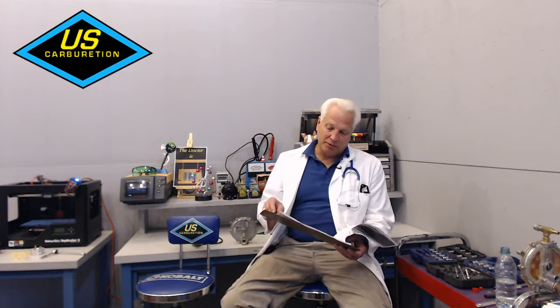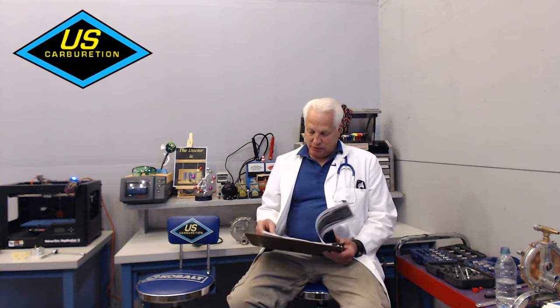We appreciate you reading the instruction manual, we often get people who don't do that. You say you apply an electrical load similar to the maximum load the generator will operate under as part of the setup. So your question boils down to, how do you apply a load without it shutting down? The answer is, you have to ramp up.